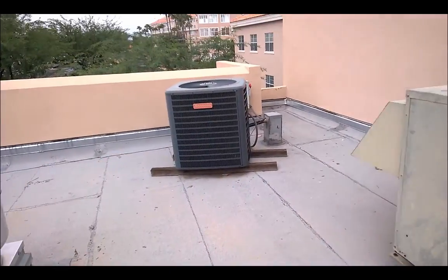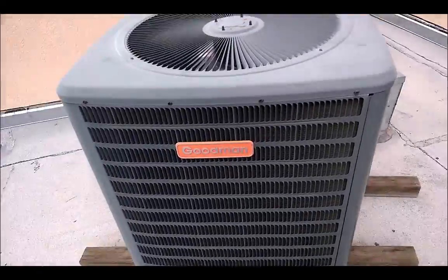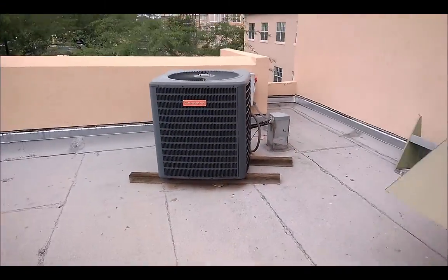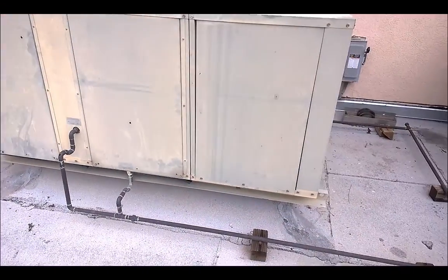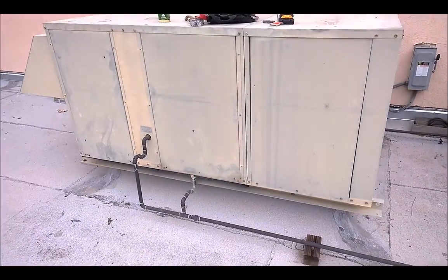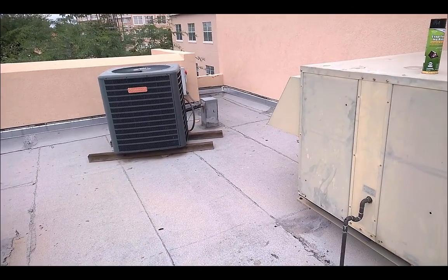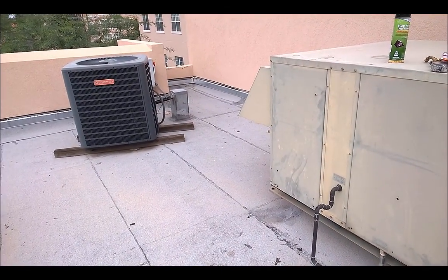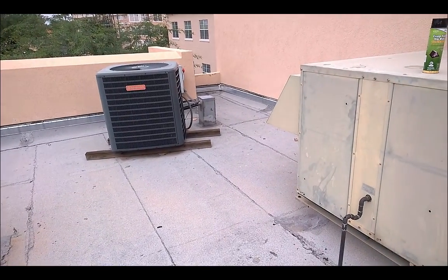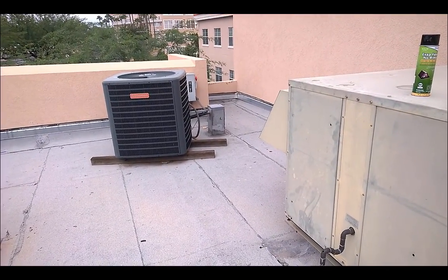This is the next generation, which is still just a four-sided coil with flimsy... It's a big improvement, but it's still just cheap — still low-bid stuff. Better than it was, quieter than it was. But I don't know, they should have built off the old design, man, with the compressor in the little compartment. Even with Bristol compressors back then, they were still quieter than the ones they made after that, when they went from a three-sided coil to a four-sided coil and put the compressor behind the coil. That's just dumb.